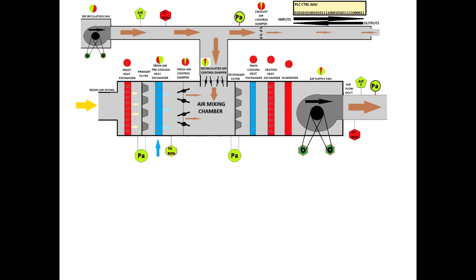If outside is very hot, you will start the pre-cooling coil, which will cool the fresh air. The recirculated air is still warm because it takes a while until the room cools down. And the cooling coil will be started as well. And the air, step by step, starts to cool down. And the room starts to cool down, but it will take a while.